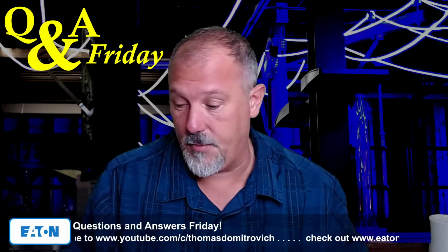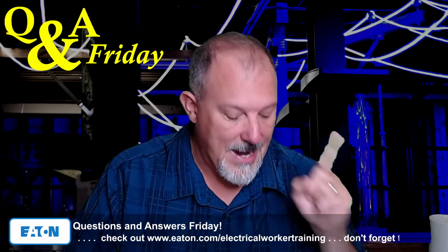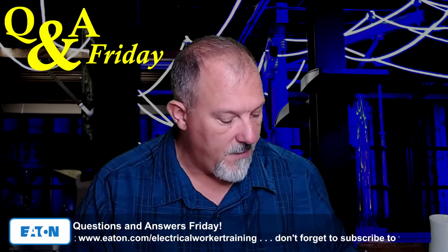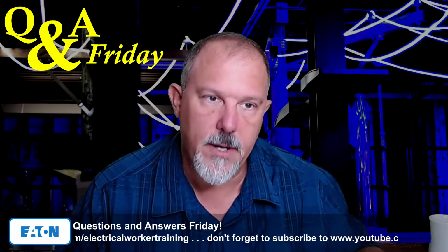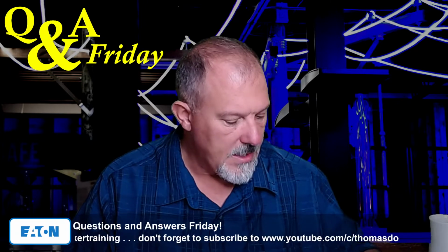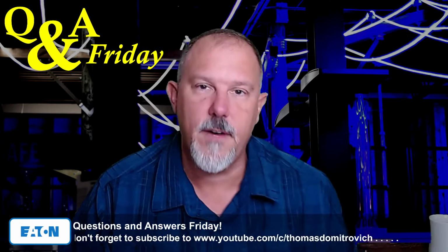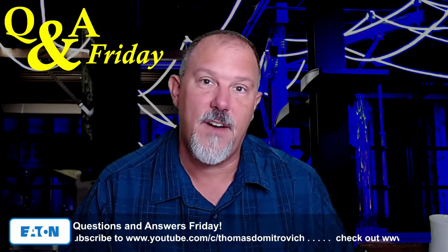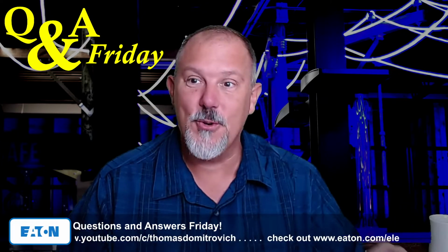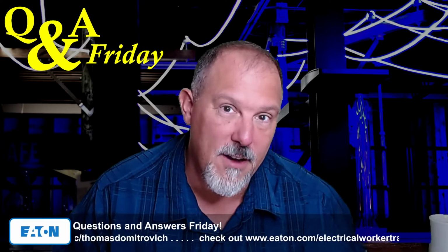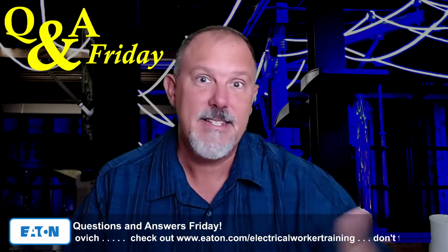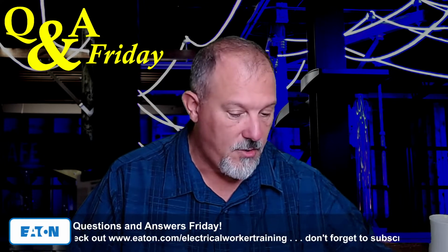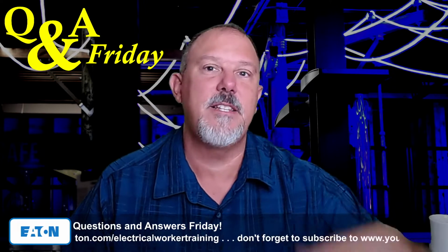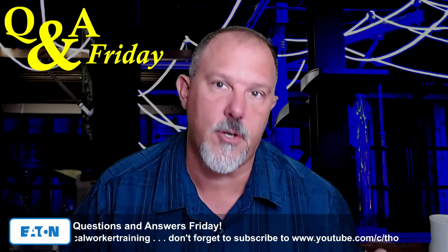But to your point, JW, if you look at 230.95, what does 230.95 tell us? 230.95 says that we need to put ground fault protection of equipment on any circuit breaker or fuse 1000 amps and above. It tells us that we can't have a setting greater than 1200 amps, but it doesn't say in 230.95 that it has to respond to ground fault current. You don't have to calculate ground fault current, compare it with the ground fault protection of equipment settings and say it does something. You don't have to do that at all because there's nothing in 230.95. Now, you do have to performance test it to make sure it works, but you don't have to prove that it will respond to ground fault current.